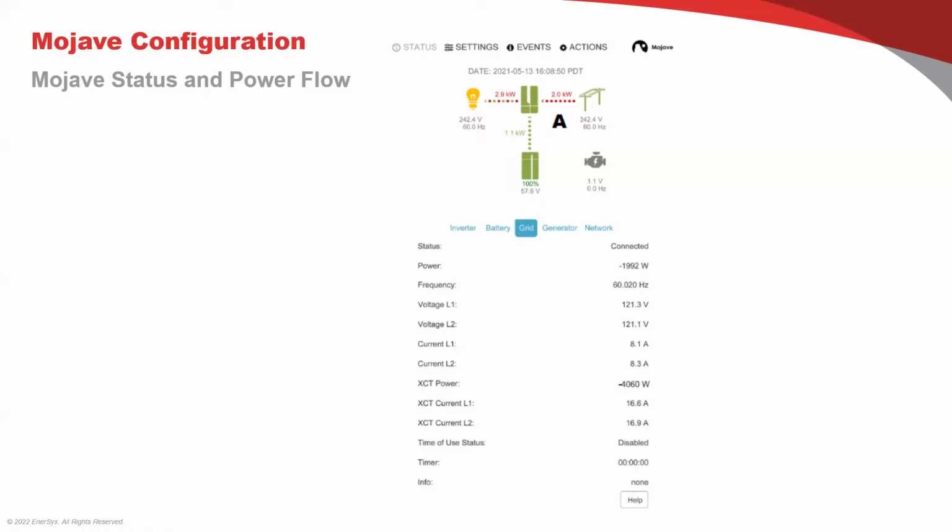One slide I did get rid of, so I'll just talk to you about it right now. In terms of battery capacity, it's 14.8, or we round up to 15 kWh nameplate. The default settings that we recommend are an 80% depth of discharge, which is pretty typical. SimpliPhi and some of the other battery manufacturers say 10,000 cycles at 80% depth of discharge, and 5,000, or even 3,500, at 100%. So we're like everybody else, but the other thing is our 10-year warranty is for 80% of nameplate capacity after 10 years. Some battery manufacturers are only 70% or even 60% of nameplate. So read that warranty very carefully.